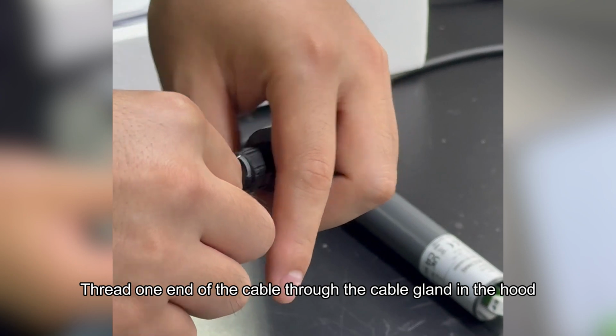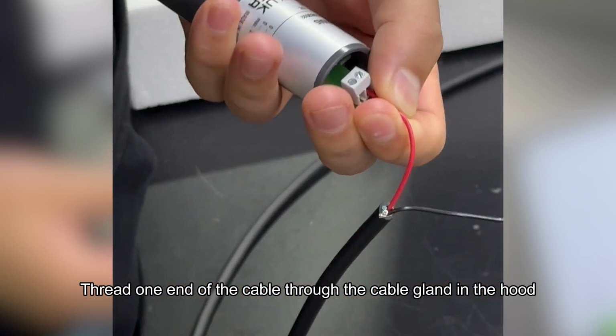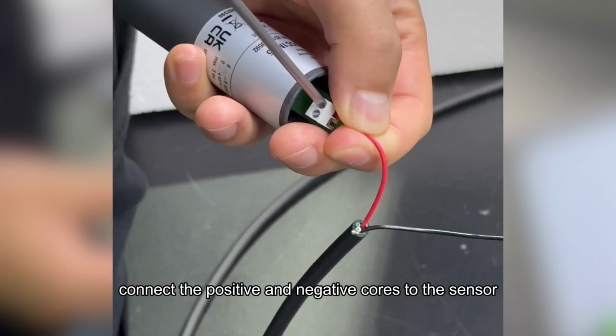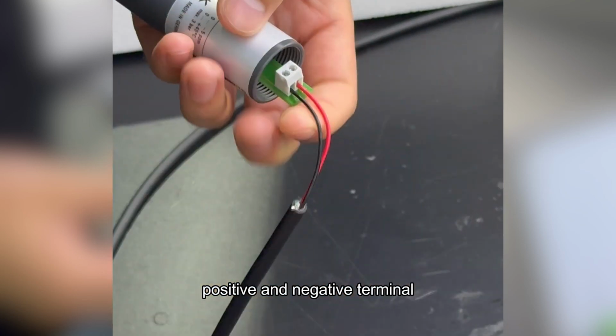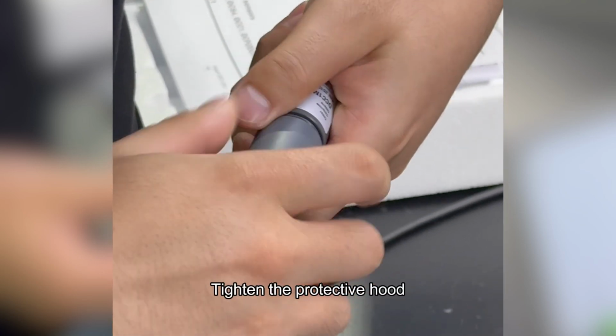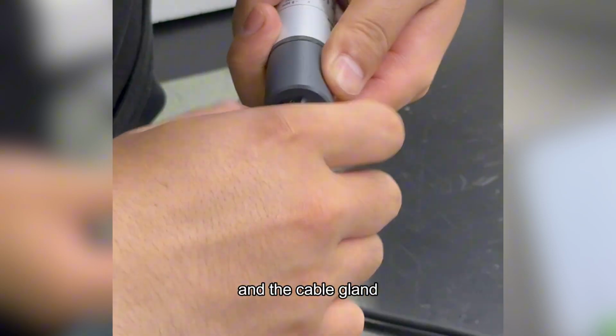Thread one end of the cable through the cable gland in the hood. Connect the positive and negative cores to the sensor positive and negative terminal. Tighten the protective hood and the cable gland.